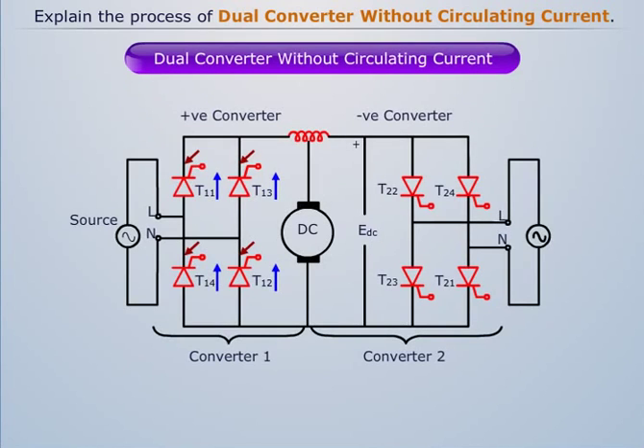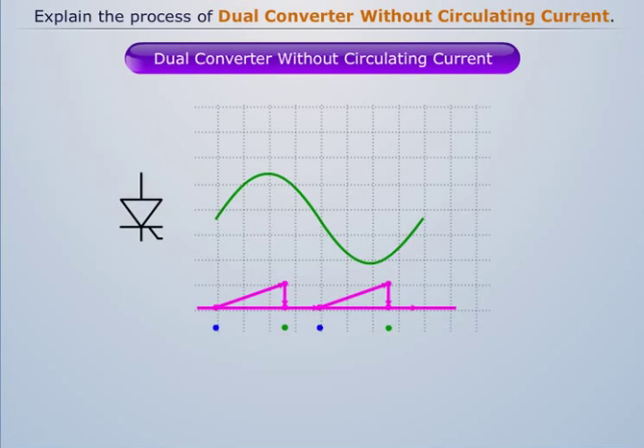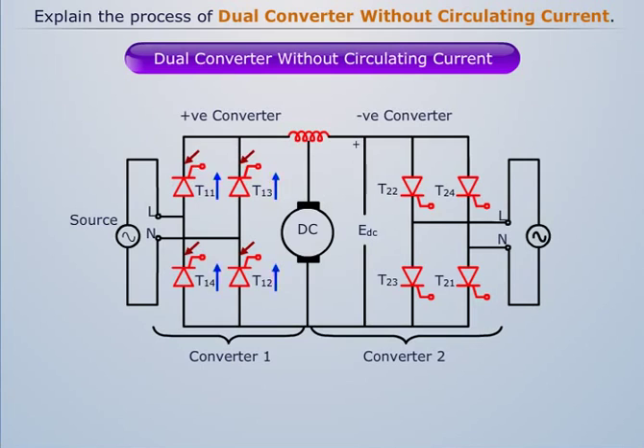In a dual converter without circulating current operating mode, the flow of circulating current is completely inhibited through automatic control of the firing pulses. So that only that converter which carries the load current is in conduction and the other converter is temporarily blocked.